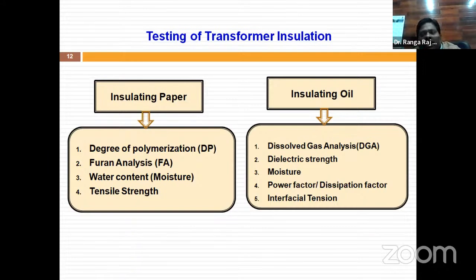This test helps in determining the various gases, and those gases generate at different levels. Some gases generate at low temperature, even at normal temperature of 50 to 60 degrees up to 90 degrees. Some gases may be produced at 150 degrees centigrade, while others, like acetylene gas, are produced at higher temperatures. If we find acetylene gas inside the oil, we can immediately conclude the oil is in a dangerous state, because that gas is only present at high temperatures. We'll study them later.